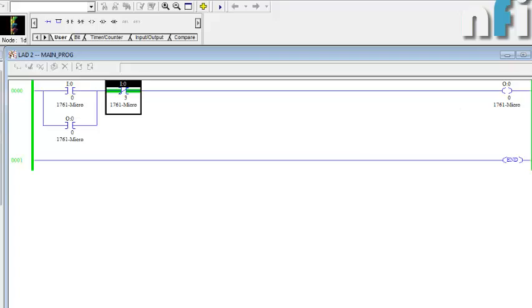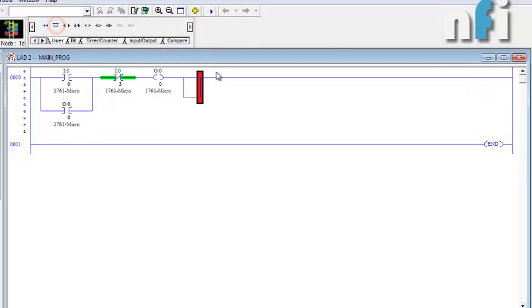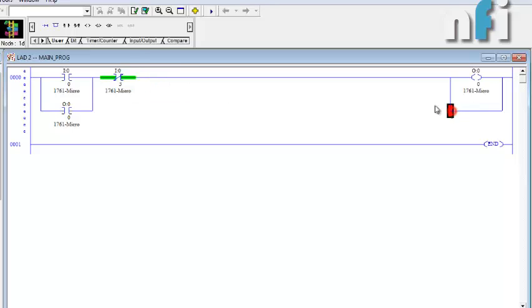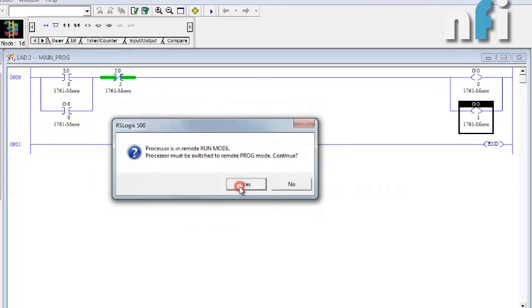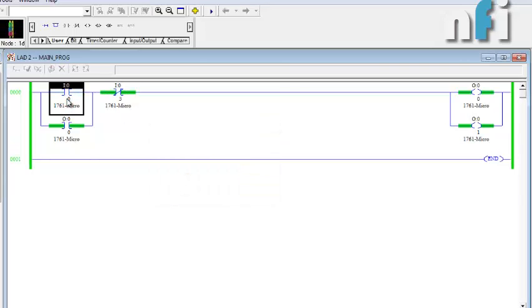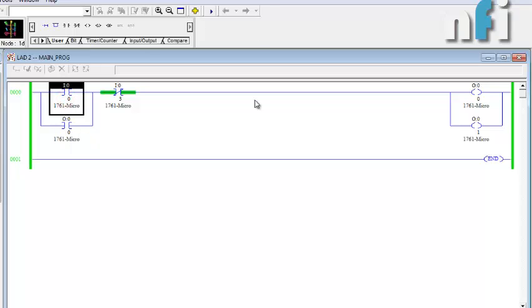Suppose you want two outputs to be latched. You can add a parallel output here — taking another output energized command and naming it O:0/1. Downloading and going online: pressing I0 latches both outputs simultaneously. Pressing I3 unlatches both. You can latch as many outputs as you need in the output branch and unlatch them all with a single input. That covers examine if closed, examine if open, and output energized — also known as NO, NC, and OUT commands.